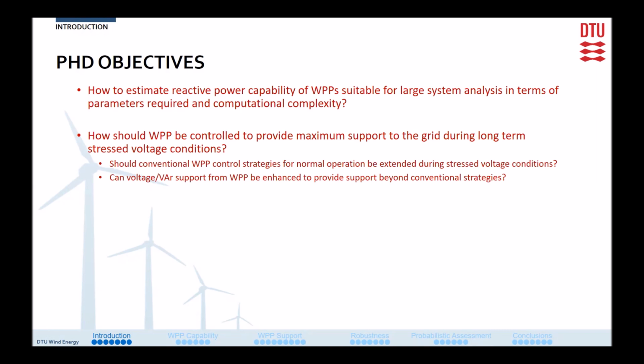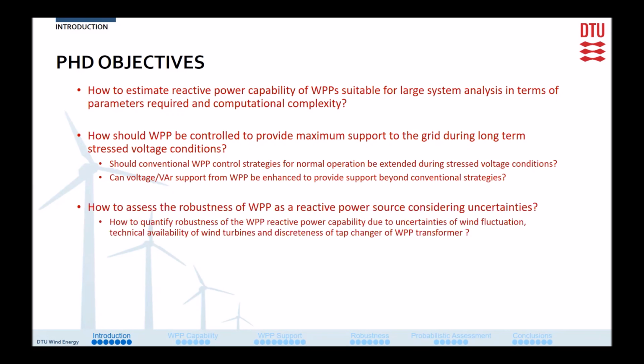Should conventional wind power plant control strategies, which are meant for normal operation, be extended during stress voltage conditions? Or can the voltage VAR support from wind power plant be enhanced in order to provide support beyond the conventional strategies? Thirdly, how to assess the robustness of wind power plant as a reactive power source, considering uncertainties? How to quantify the robustness of wind power plant reactive power capability due to uncertainties like wind fluctuation, technical availability of wind turbines, and discrete control action of the wind power plant transformer.